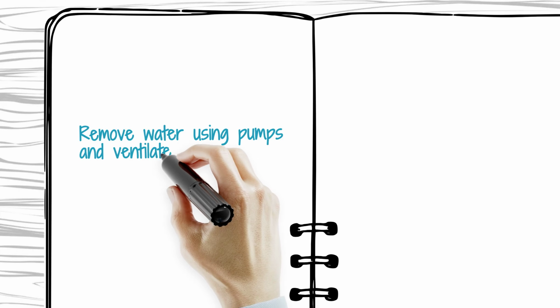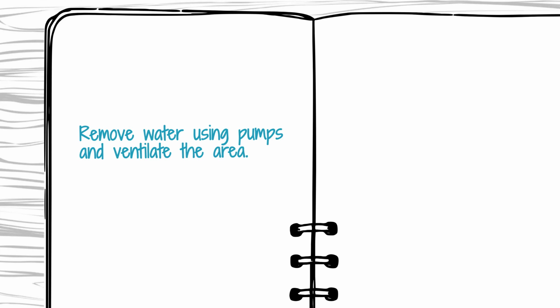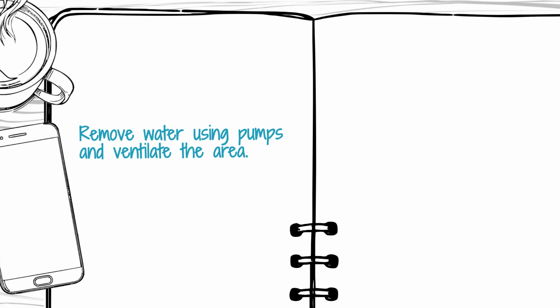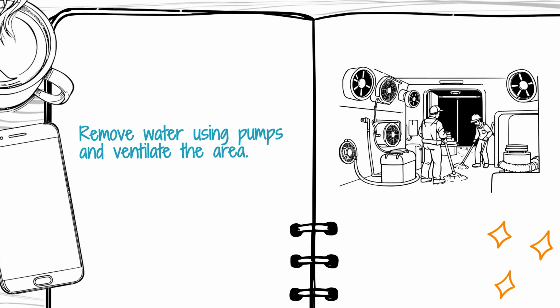The third step is water removal and initial cleanup. Prioritize stopping the source of water ingress. Use pumps, eductors, and mops to remove the water until the affected equipment is no longer submerged. Ventilate the area thoroughly to remove any potentially hazardous fumes or moisture-laden air.